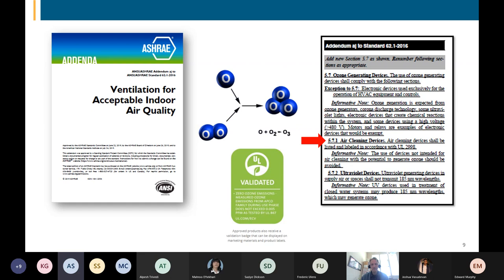Rarely, if ever, will you find indoor environments provided with ionization technology that come anywhere near that maximum level. Typically, the 400 ions per cubic centimeter, positive and negative, are on the low end baseline of what you might find in the indoor air through natural occurrences, such as bringing in outdoor air that's more highly ionized. Does that answer the question? And if not, I'll be happy to talk more about it, or we can cover it in Q&A.